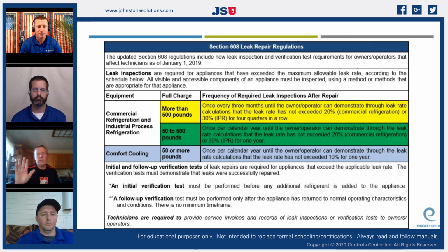And I try to say, keep it simple. Comfort cooling, 50 pounds or more, 10% leak rate. Commercial refrigeration, 50 to 500 pounds, it's 20 or 30%, depending on whether it's considered industrial process or commercial refrigeration. More than 500 pounds is 30% or 20%, considering what category it falls into.